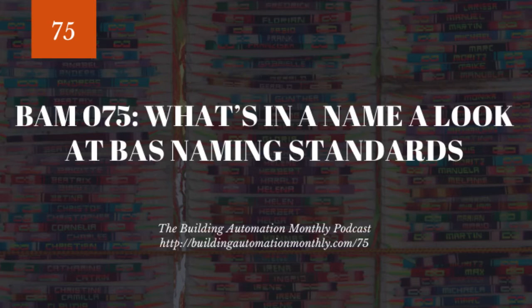Now, immediately I can look at that and tell what building it is, what room it is, what floor it is, and what type of device it is. That makes things very, very simple. If I get an alarm and I look at it, the worst thing in the world is when you need a decoder ring to make sense of the different names on that fully qualified reference. Basically, that is the data reference that the database and the whole BAS system uses. It's not the short name, it's the actual long name. And that's often what shows up in alarms, on trends, in reports, etc. So, as I said, the first is that it's got to be clear.